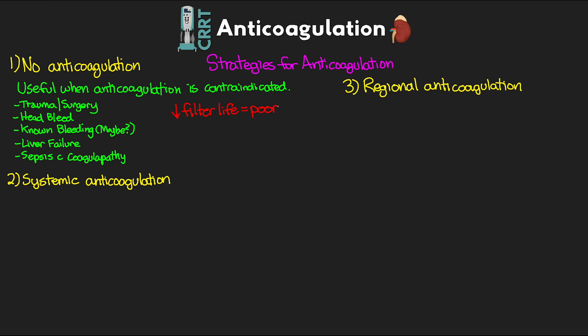Another potential downside of no anticoagulation is that if the filter completely clots off and we're not able to return the blood while it's still safe, almost half a unit of blood is going to be lost. If this is happening frequently, this can obviously lead to a need for transfusion for our patients.